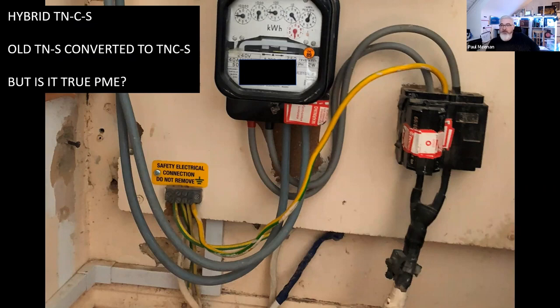By the way, you're bang on right, because I raised that with the regional engineer who wrote me a letter telling me that once I've dug my driveway up, they'll come and put a new service in. But they've done nothing at the other end, have they, to create the system? No, and this is the point. If you draw a map on your local street map and you just branch loads of cables in, then they're old PILC SNEs. The PME conversion will be either jointed repairs or a link at the substation and a link in the cutout.